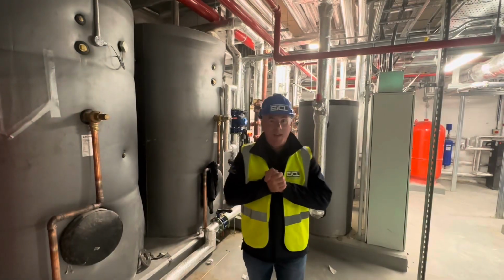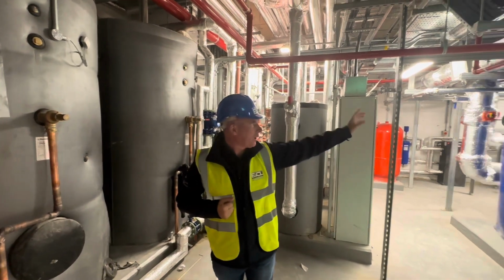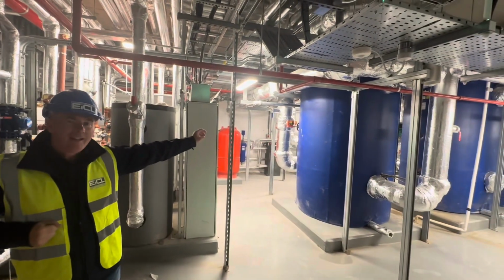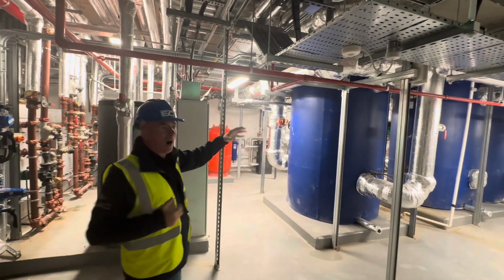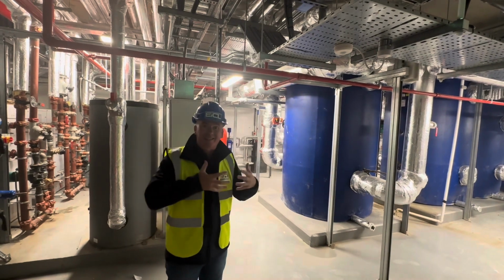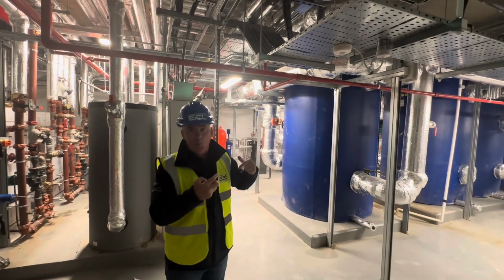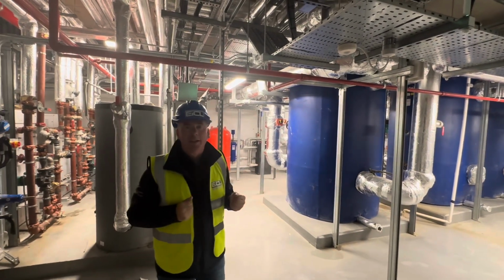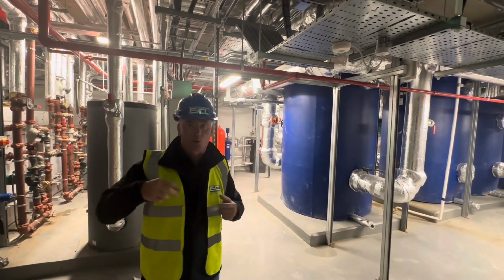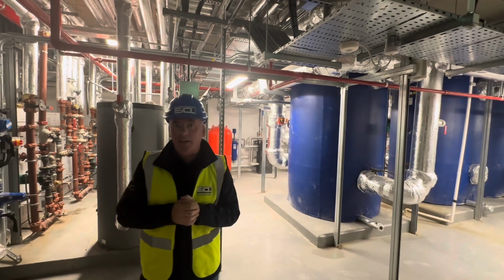So as you can see, we're in the basement plant room here. This is where we have our buffer tanks for Fiorini. These buffer tanks, by the way, are designed in a way that they're decoupling tanks. So we've two pipes in, two pipes out to separate a primary loop from a secondary loop. I've done an article, a specific article, by the way, on buffer tanks. So just go onto LinkedIn, look at my articles, and you'll see that there.